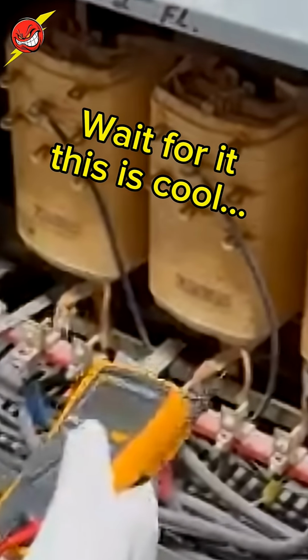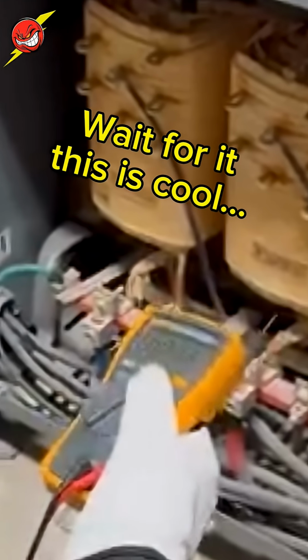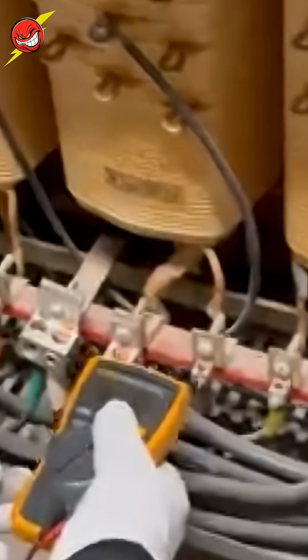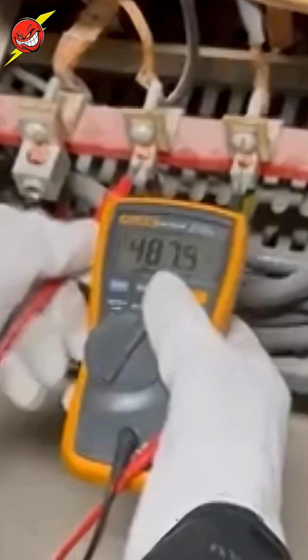Alright, so I got this transformer opened up right now. It's a 480 Delta primary, 208/120 Y secondary. Let's go ahead and take some voltage readings. I'm going to go from H1 to H2, 481. H1 to H3, 487, H2 to H3, 491.